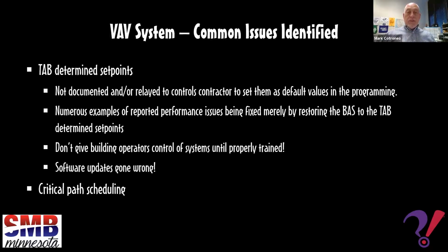Another item is the critical path scheduling. For successful and timely project completion, critical path scheduling needs to be followed. The temperature control system needs to be somewhat complete in order for TAB to progress in a timely manner. The VAV boxes need to be under control and mapped to the BAS. The air handling units and exhaust fans need to be connected to the BAS so that they can be turned on and off and dampers manipulated. If the temperature control is not working ahead of TAB, it will cause delay in closing out the project.